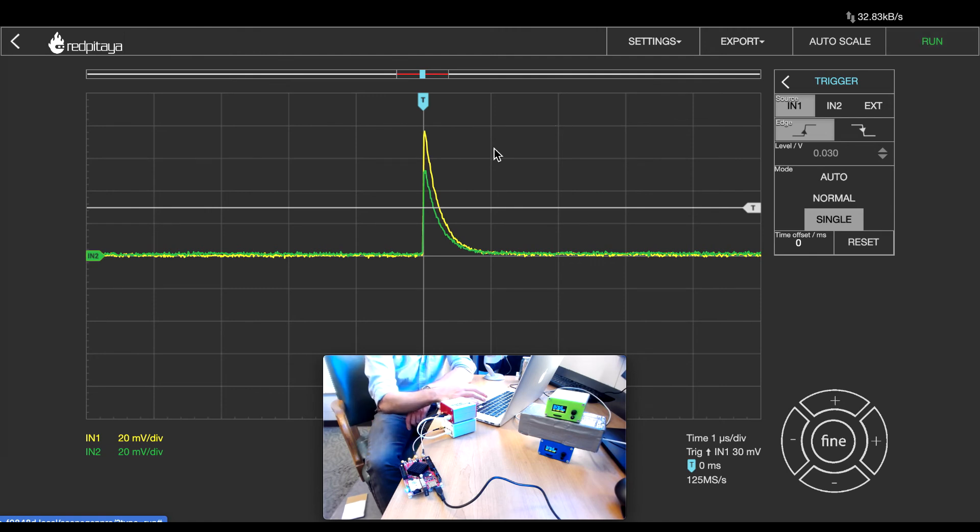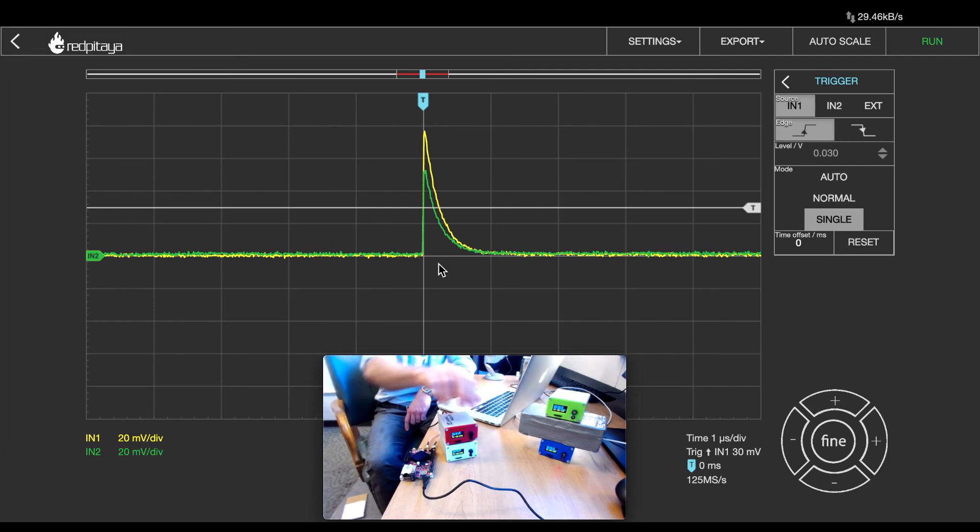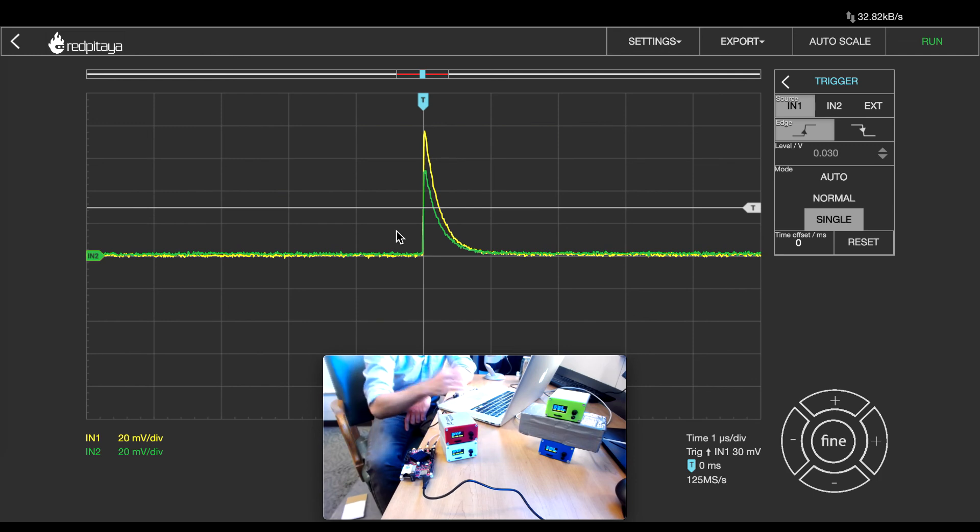Here's one example. You can see both detectors triggered at the same time. Input 1 and input 2 both show a pulse in coincident with each other. Had you been watching the coincident LEDs here, you would have noticed that for this particular event, those two red lights would have flashed at the same time, and that event that was saved to the detector would have been labeled as coincident.